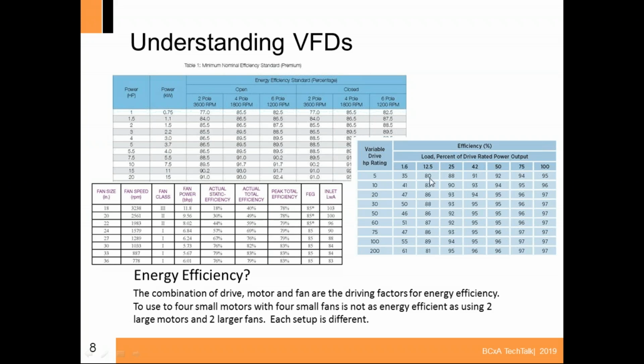Then we start taking into account the efficiency of the drive. This is your drive efficiency and the horsepower. As you can see, when the VFD is actually going full output, it runs the most efficient. When it starts coming back, let's say at 25%, that's running at 15 hertz, it loses quite a bit of efficiency.